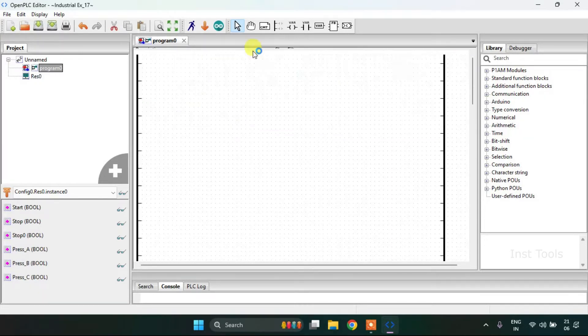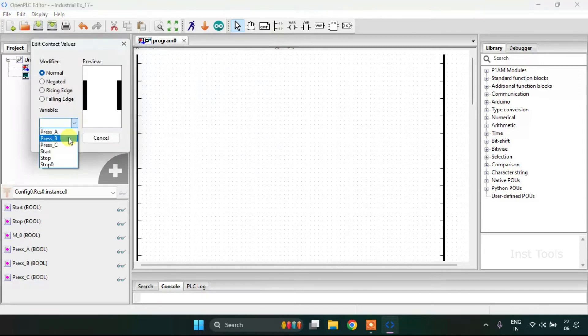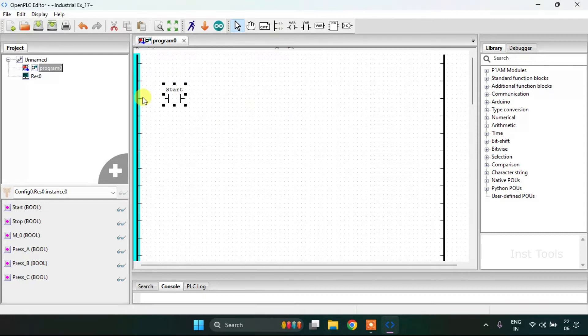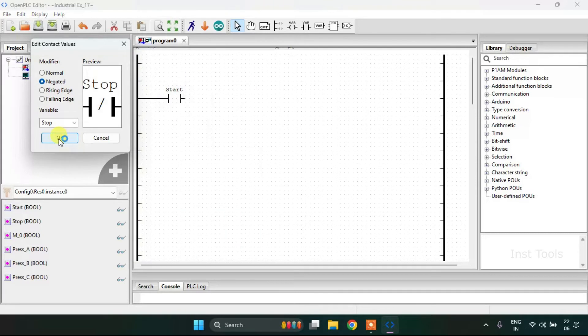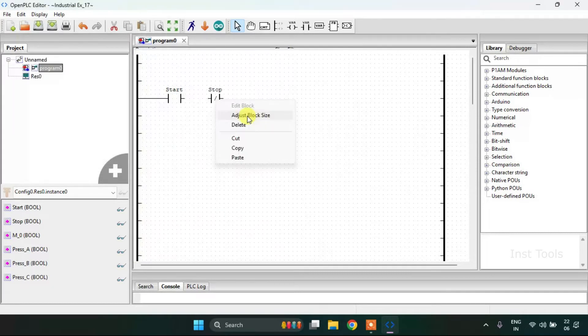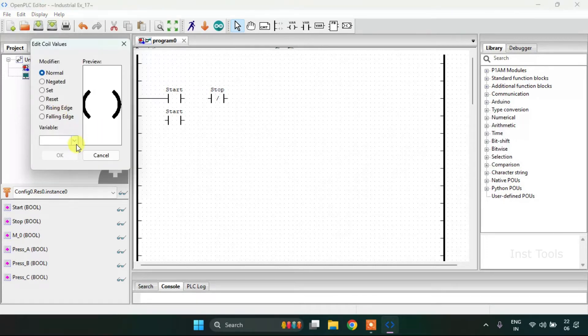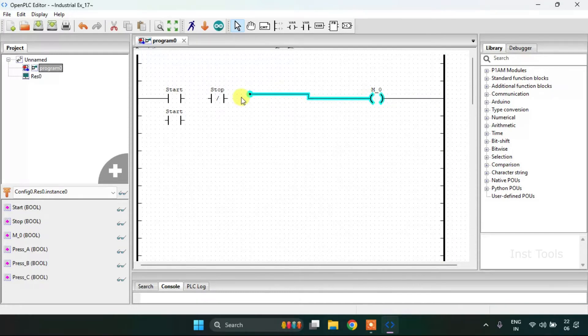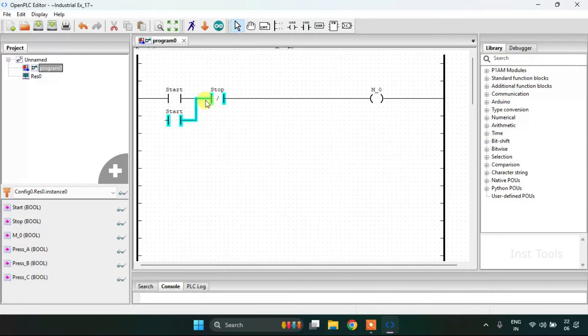I will drag this up and I will start with the contact here which is going to be the start. In my first rung, I just need to create a push button and in series the stop switch which is going to be normally closed contact. And on the right side I will add a coil. I'll join these pins here. And I'm going to change or modify the contact here. My first rung is complete.